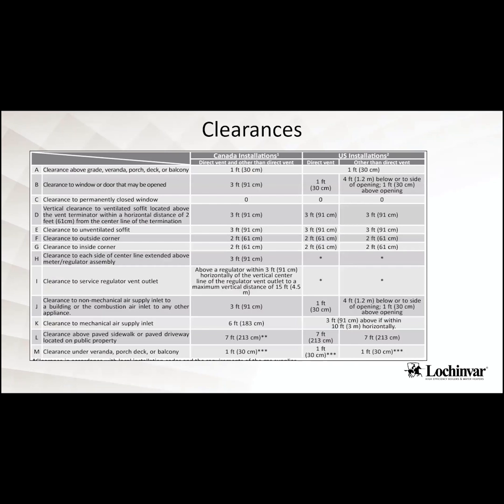All righty. So with this unit, this is the National Fuel Gas Code clearances. This is the same for every manufacturer that's out there. So in a direct vent and then other than direct vent on there. You're 1 foot from a clearance to a window or a door that can be opened. The biggest questions I always get on this are J and K down here. So clearance to a non-mechanical air inlet supply of a building or the combustion air inlet to any other appliance.